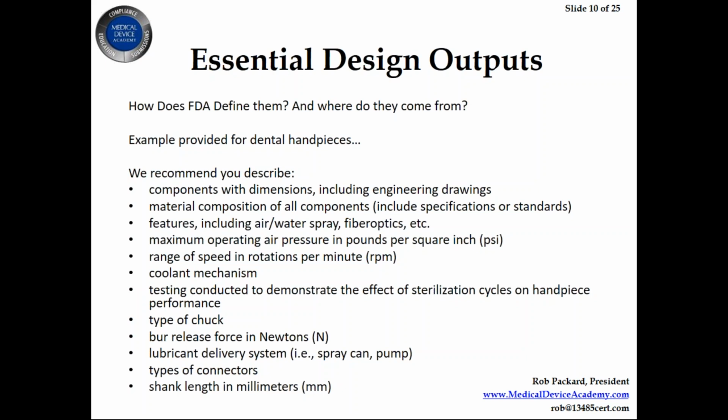And I'm wondering if the person is more familiar with European products where we have essential principles or essential requirements, which would be Annex 1 in the MDD. We don't have that for the FDA. We don't have essential requirements for safety and effectiveness for devices as a whole. However, on a case-by-case basis, there are special controls guidances for some Class 2 devices that say what those testing requirements are and what performance criteria there are and what safety and testing they might have to do.